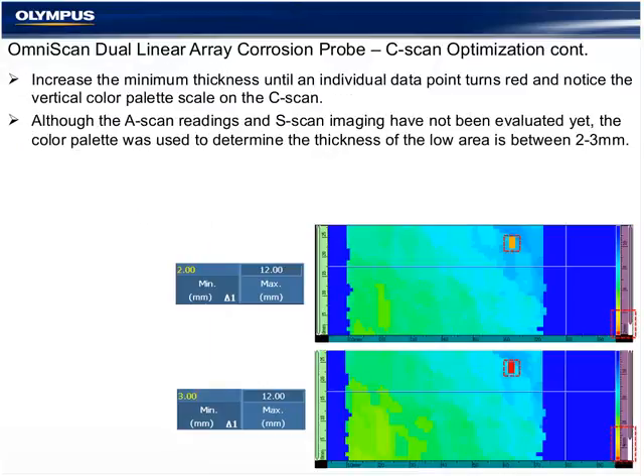As I start to change that and move it either directly in the software 1 millimeter at a time, or by taking my mouse or finger on the touch screen and dragging this up, I'm going to change the contrast of the color palette until my first red pixels appear in the data. In this case, going from 2 millimeters to 3 millimeters, I can see the pixel turn to red. So I know I have at least one data point between 2 and 3 millimeters and no data points less than 2 millimeters in the C-scan.